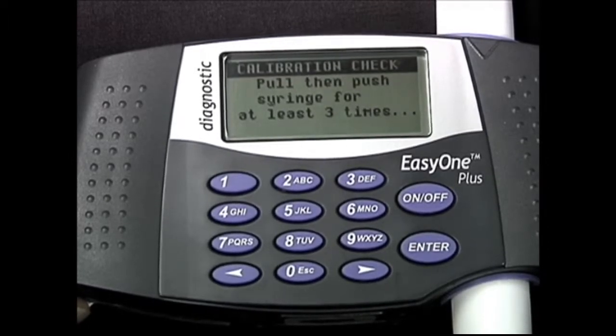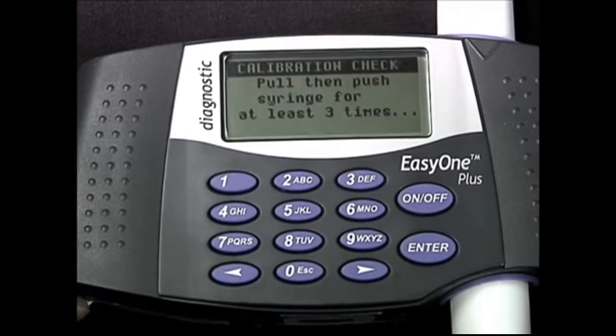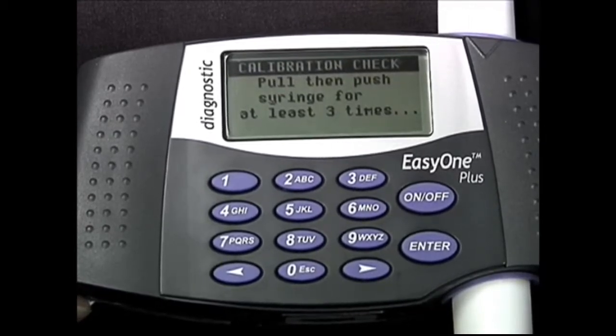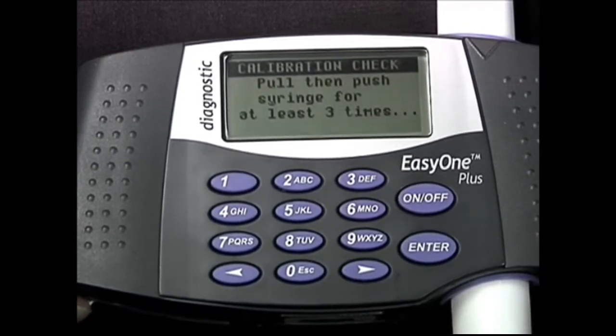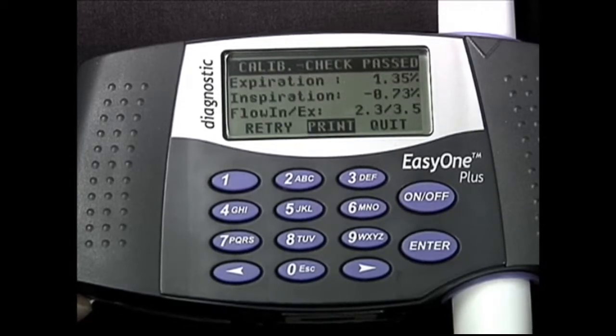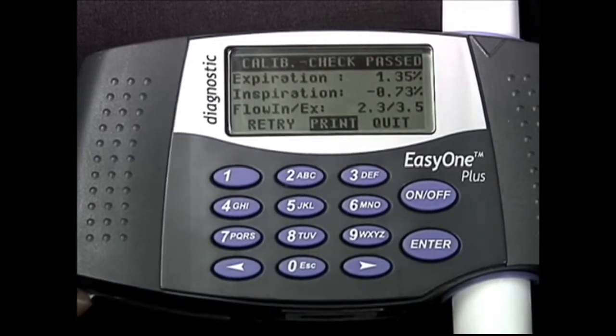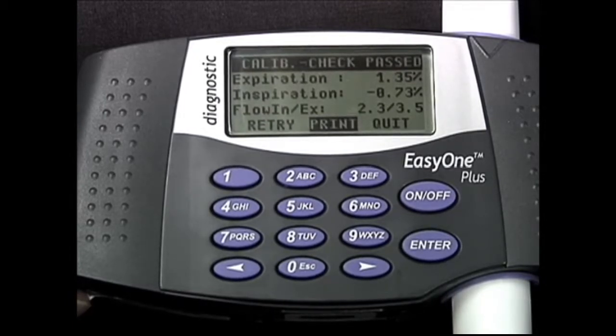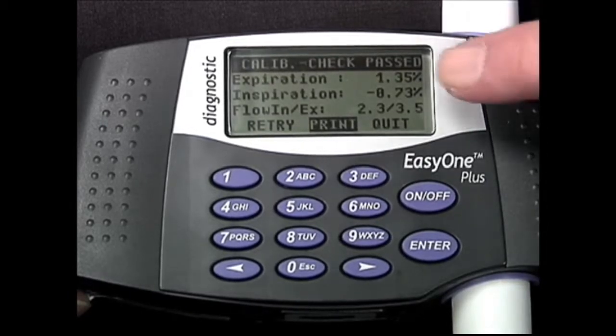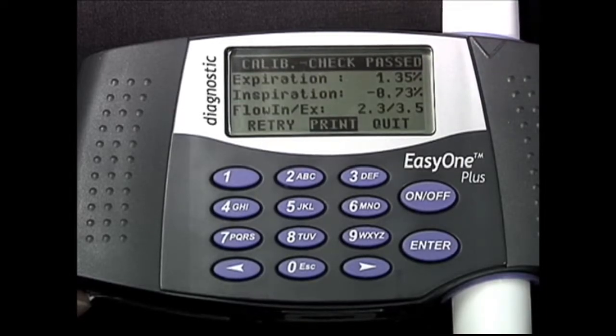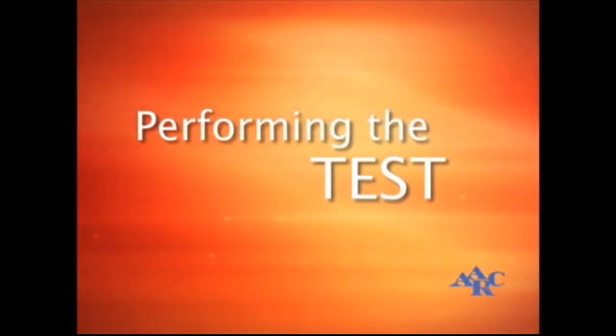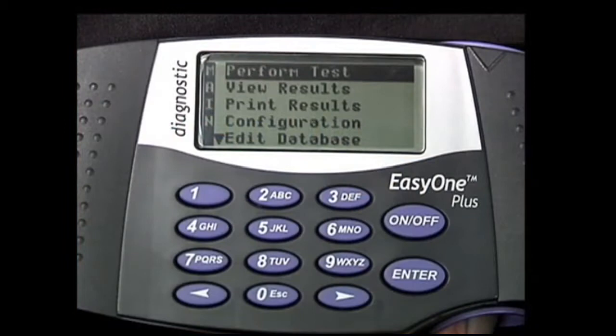Be sure that you use the full travel of the syringe as you're doing this. Try to avoid banging the syringe and going too rapidly during the calibration check. You need to make sure that the expiration and inspiration variability are less than 3.5%. As long as these two numbers are less than 3.5%, you're done for the calibration for the day. You're now ready to perform a test.